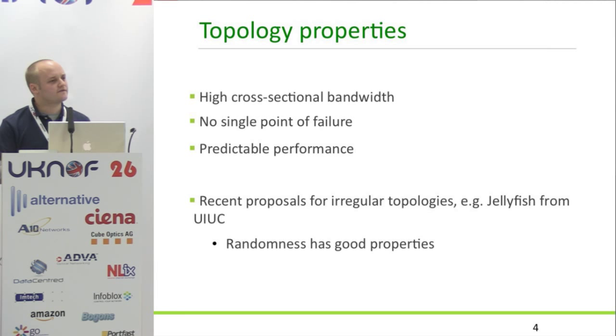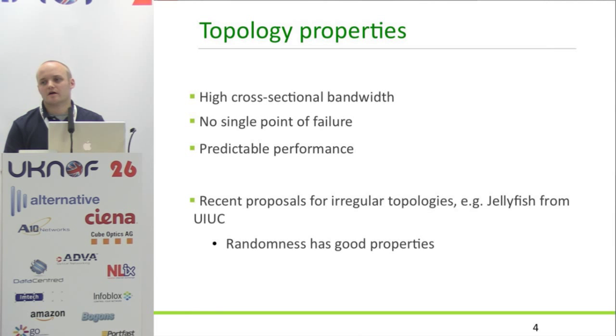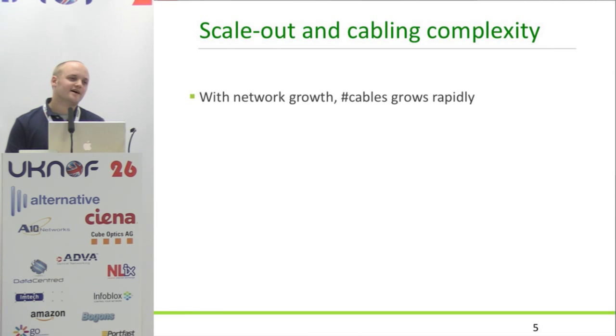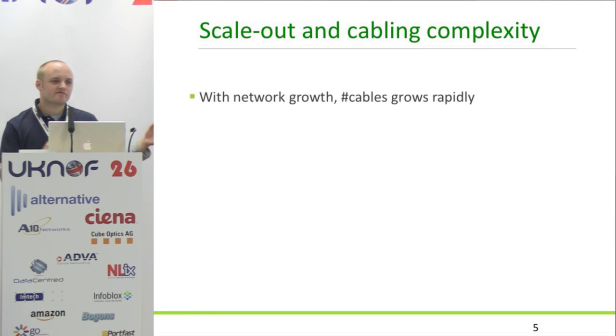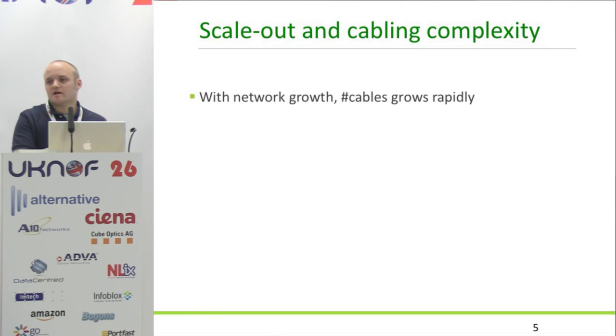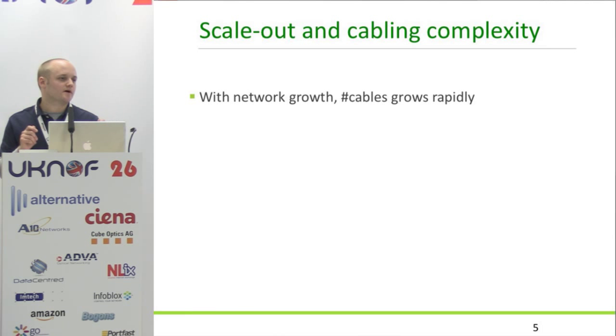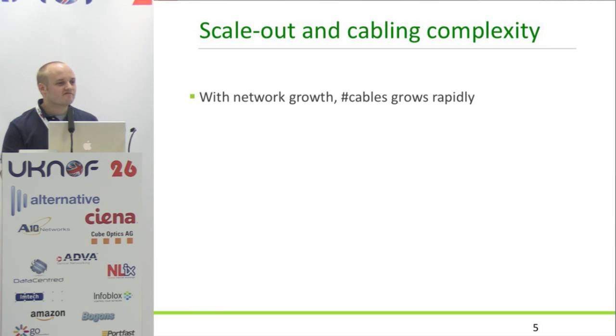It also means there are very few single points of failure. A whole spine can vanish and you'll know exactly what impact that will have on your application. As we move to this spine-leaf design, it can become a bit of a nightmare for cabling. With some of these big web properties, instead of their engineers racking and stacking boxes, they're ordering rows of racks to be prefabricated elsewhere — maybe 48 back-to-back servers and two top-of-rack switches — and then delivered. But maybe there are instances where the cabling is wrong, which can be a real nightmare to debug in a data center with 500 or 600 racks.